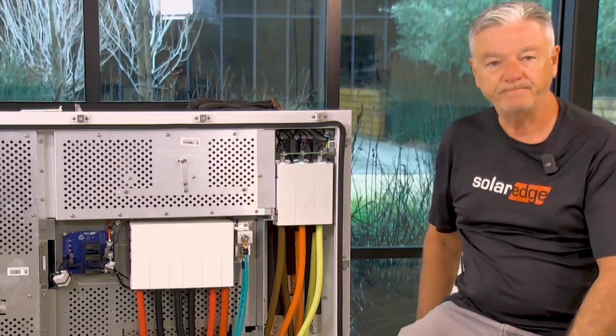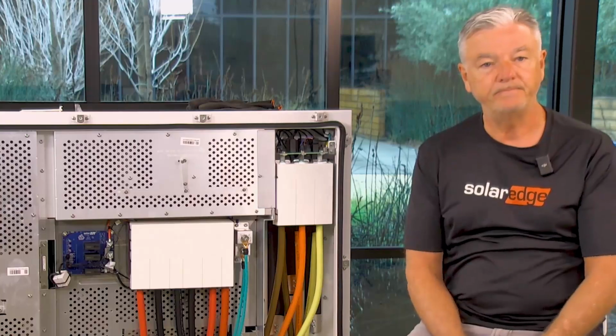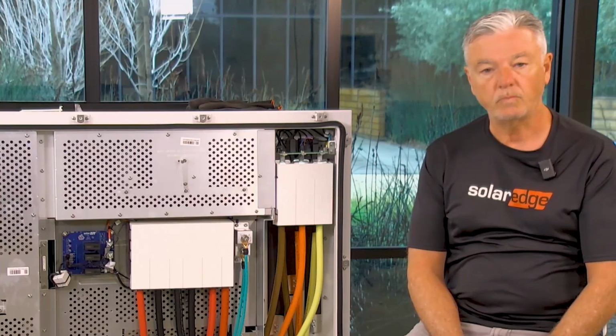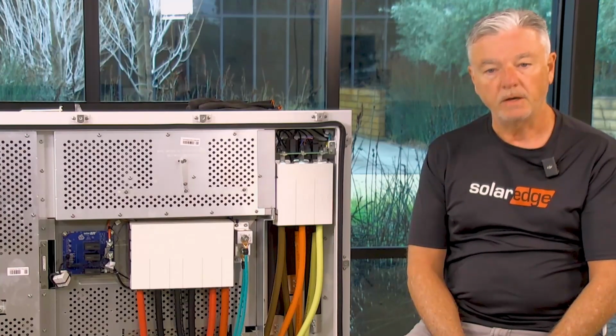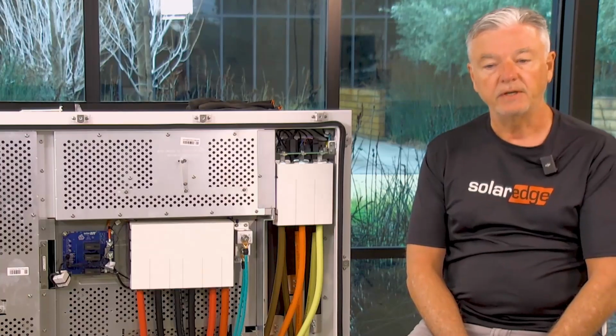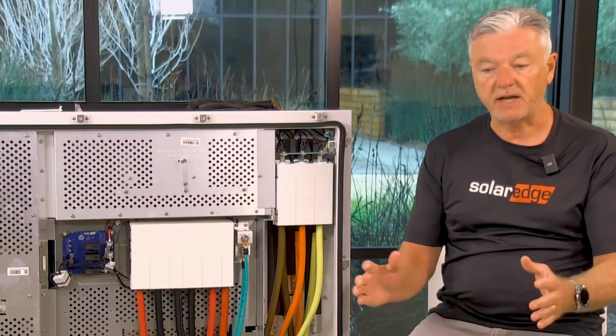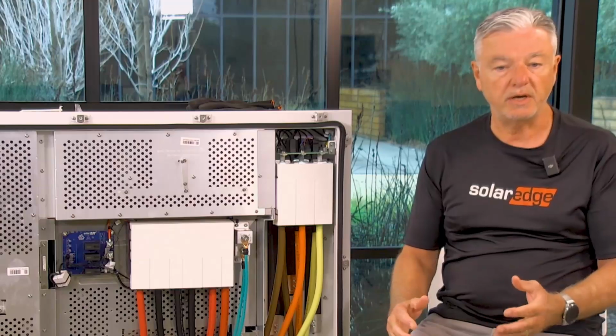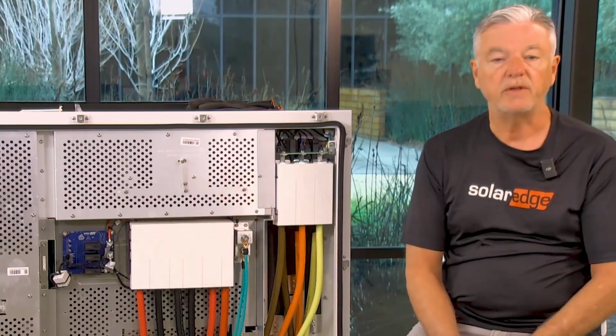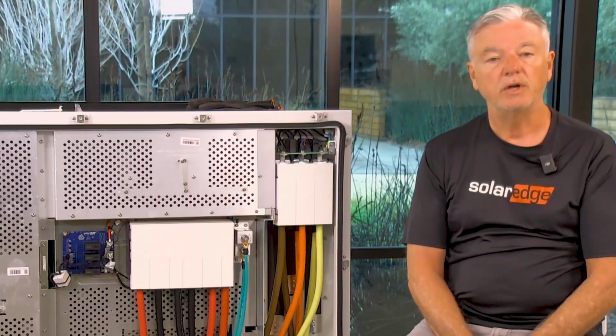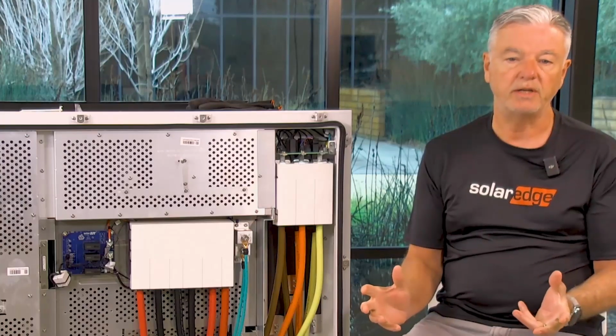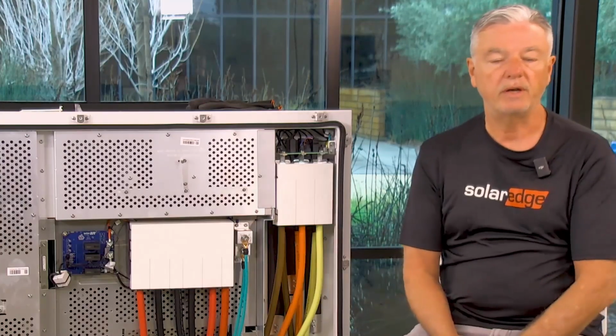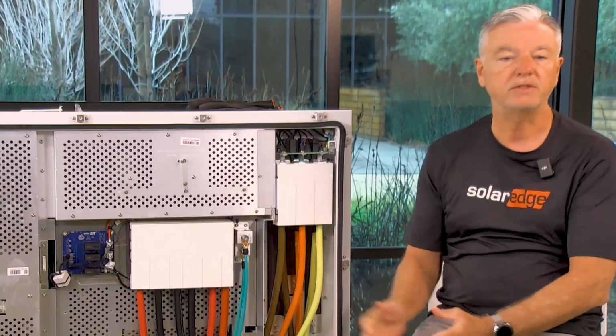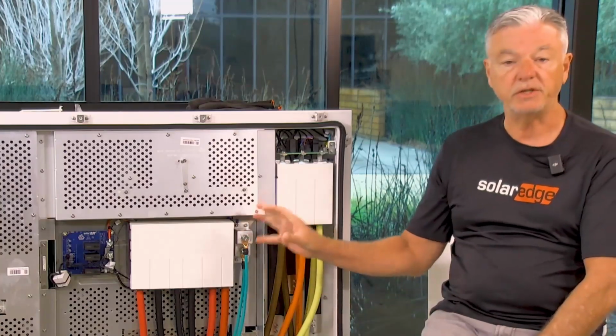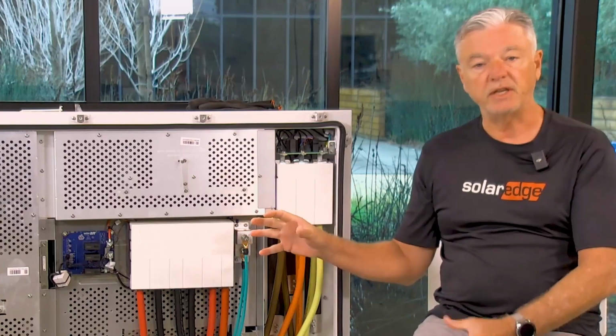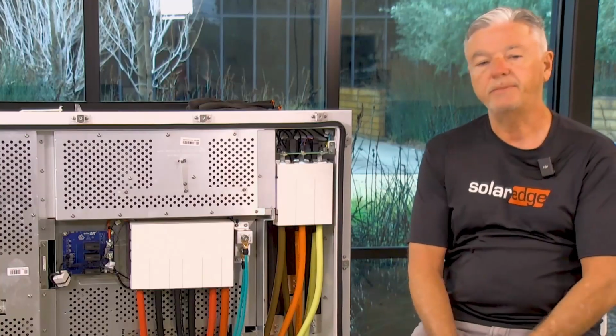Are there any specific cell kits that we're supposed to be using with these? Or are there commercial specific cell kits? There are. We have commercial cell kits of particular sizes for 200 kilowatts, 1,000 kilowatts, and up to 2,500 kilowatts. So depending on the size of the project that you're working on, you would order the correct cellular card that would apply to the system. And it would be installed in the leader inverter in an installation that had multiple inverters connected.